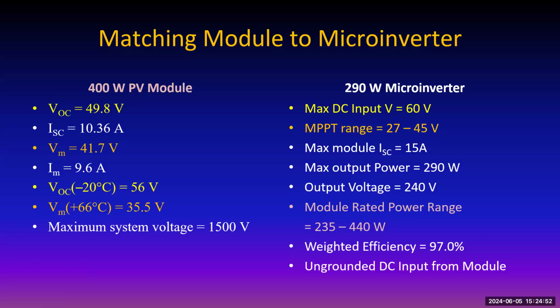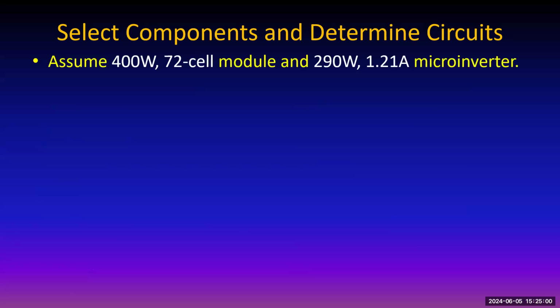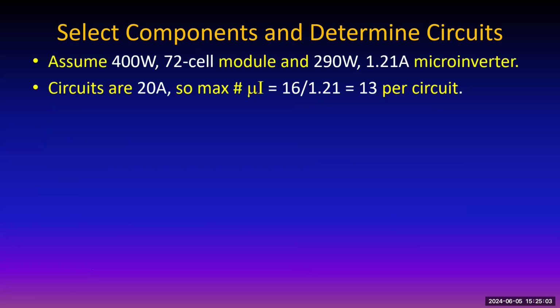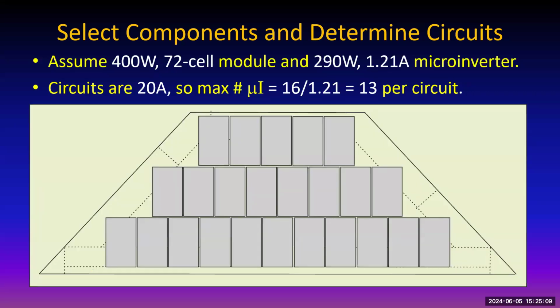Okay, so we've got a matched module and microinverter. So now we select the rest of the components. We got the module, we got the microinverter. The circuits are going to be 20 amp circuits because the manufacturer of the microinverter provides the wiring harness to do that. It's open wiring up underneath the modules. No conduits or anything up there. Just the wires are hanging loose, open, with wiring that's rated for very heavy duty insulation on them, type PV. And as long as it's properly supported under the modules, it's fine.